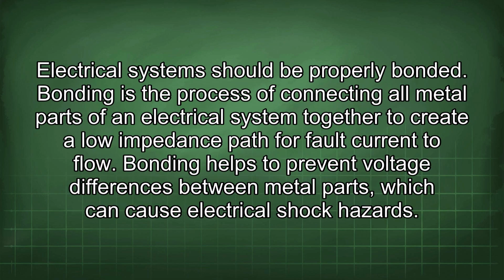Electrical systems should be properly bonded. Bonding is the process of connecting all metal parts of an electrical system together to create a low impedance path for fault current to flow. Bonding helps to prevent voltage differences between metal parts, which can cause electrical shock hazards.